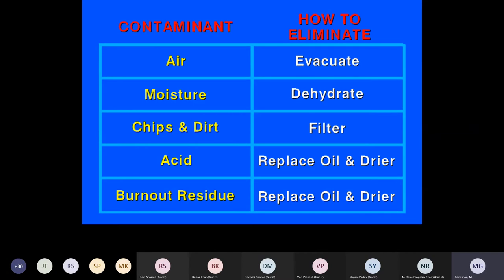Moisture, you know, any moisture in our system, we talk about it in terms of ppm, parts per million. It should not even be that much. Maximum 50 ppm is allowed in an oil. So imagine, 99.95% is the purity of the refrigerant. So if we did not do the evacuation properly and a little remained, and somewhere there is a leak.